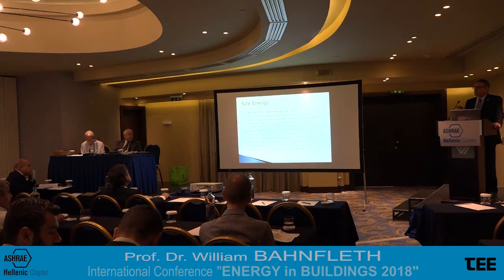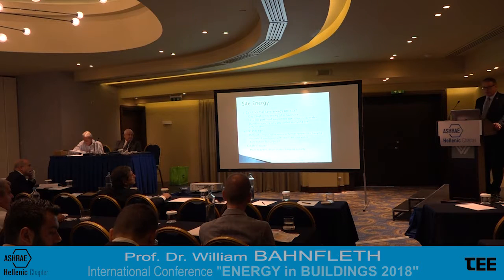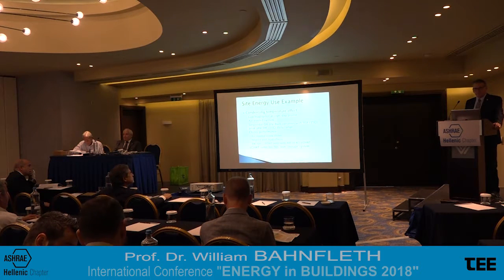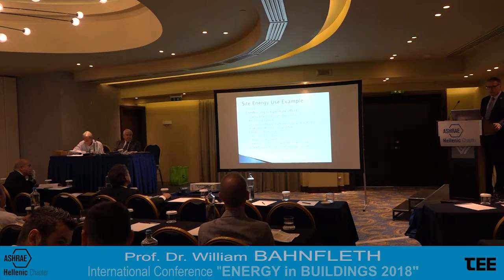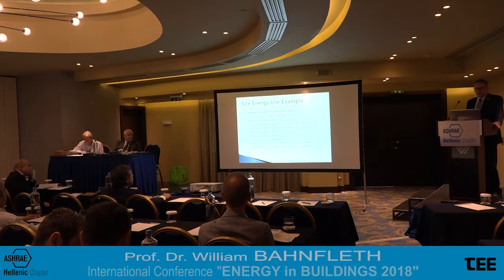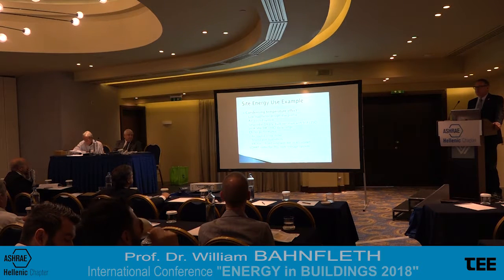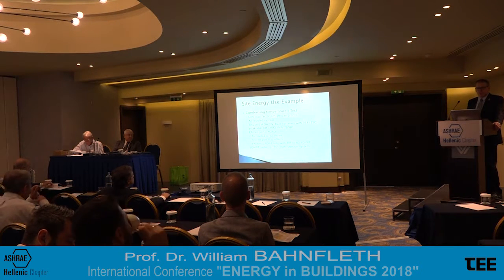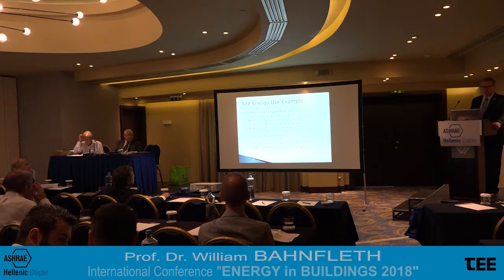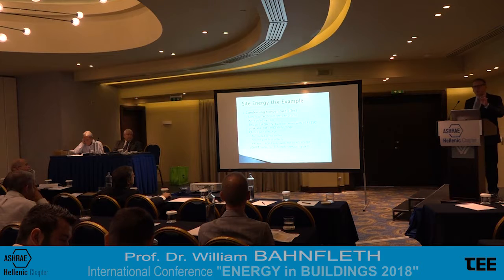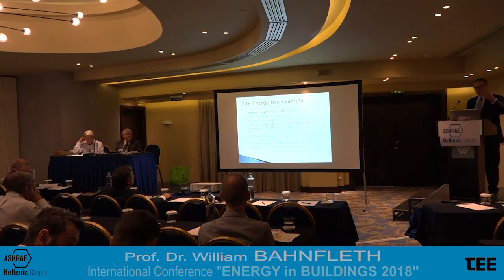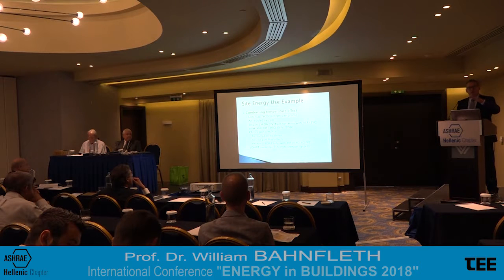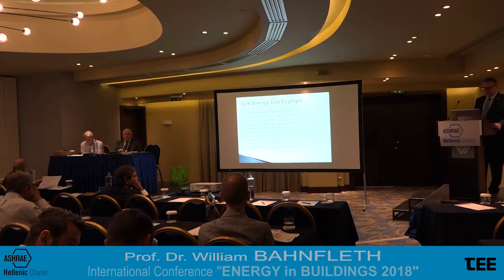Chilled water, because it doesn't necessarily alter the operating temperatures of the system, tends to be very compatible with a low energy approach because there's not really a charging penalty. So we're going to look at an air-cooled example here, and I'm going to assume that we're dealing with a chilled water storage type of system, so that we're not trying to account for a change in the evaporating temperature. I'm going to compare how much energy it would take for a given air-cooled chiller to meet a certain cooling load without storage, as opposed to having level load storage that will flatten the cooling load over the course of the day.